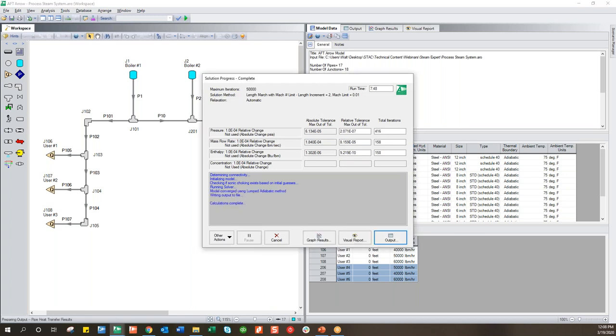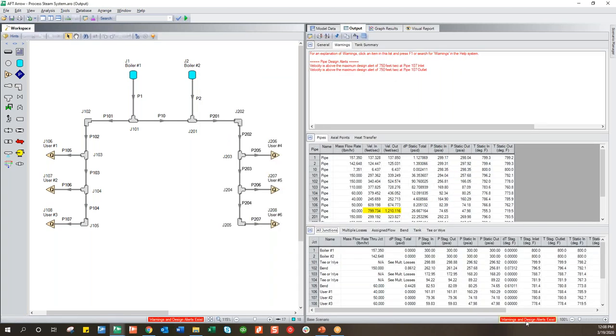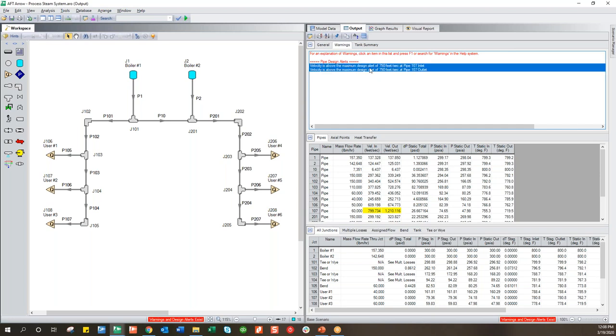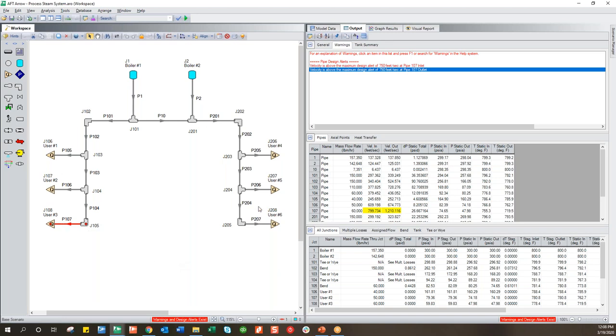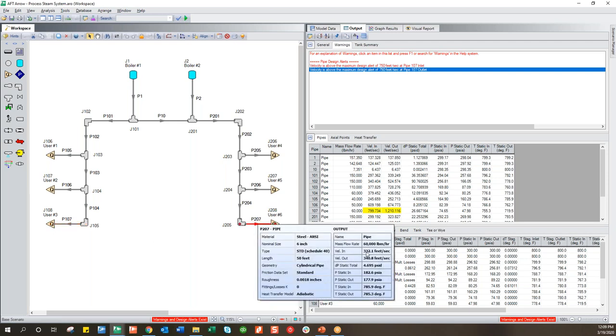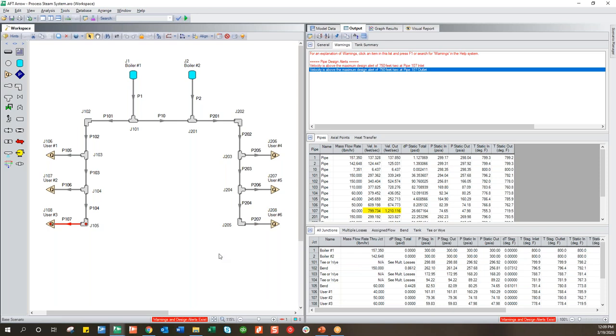Oh no, I've got a warning. Velocity is above the maximum design alert of 750 feet per second at the inlet and outlet of P107 — right here. Look at those velocities — that's way higher than what I wanted. I only see it in this pipe, not the rest of the system. As I said, they're nearly symmetrical. But if I look at this pipe: 60,000 pounds per hour coming out here and 60,000 pounds per hour coming out here, yet this is only 300 feet per second and this is 800 — almost a threefold increase just because of certain changing conditions.